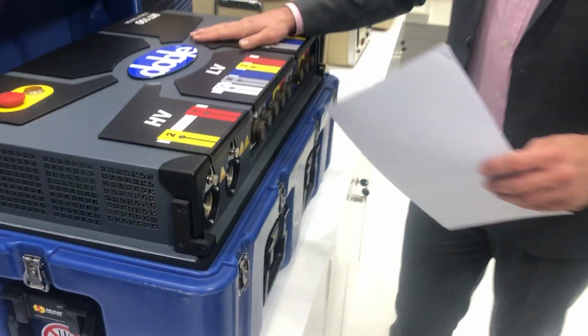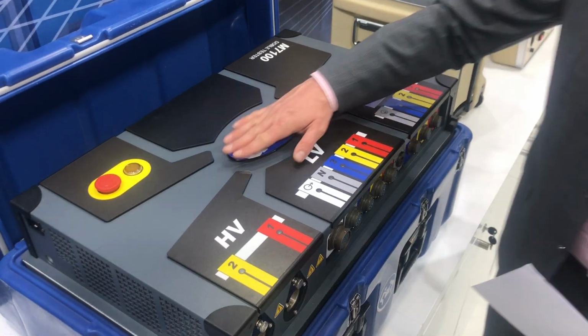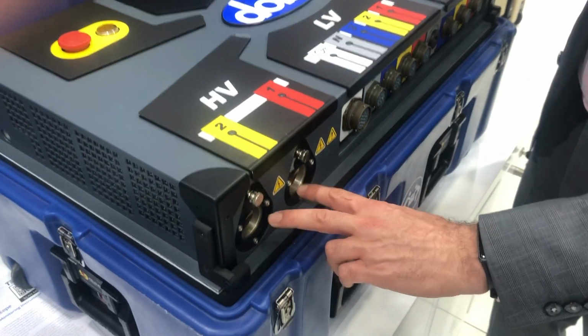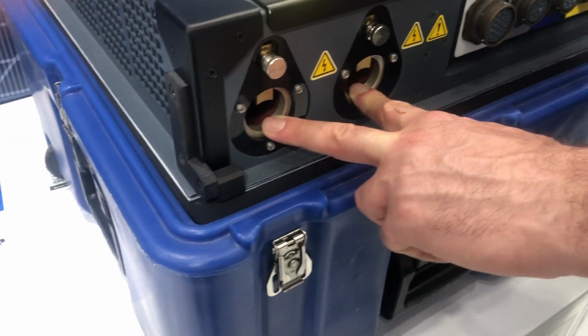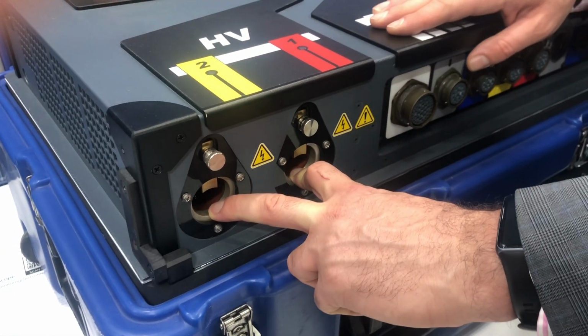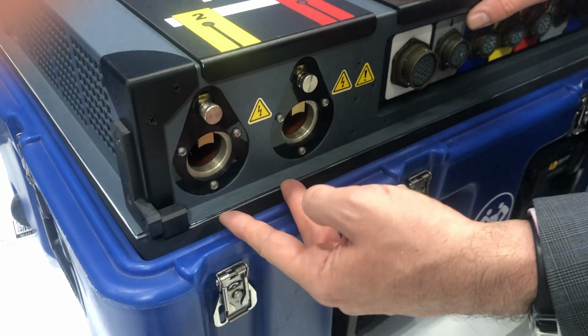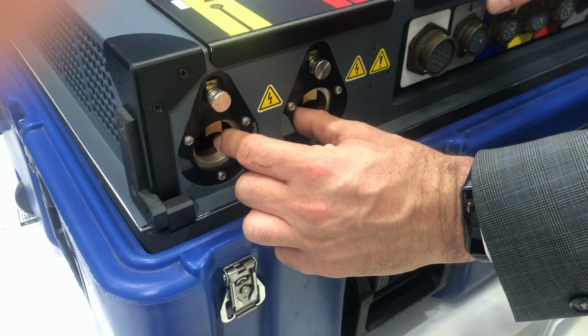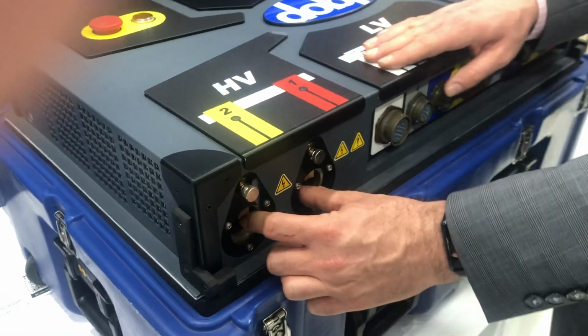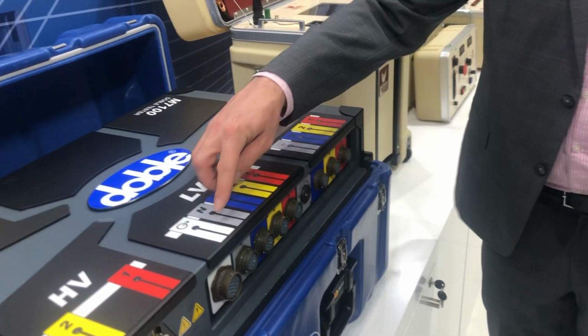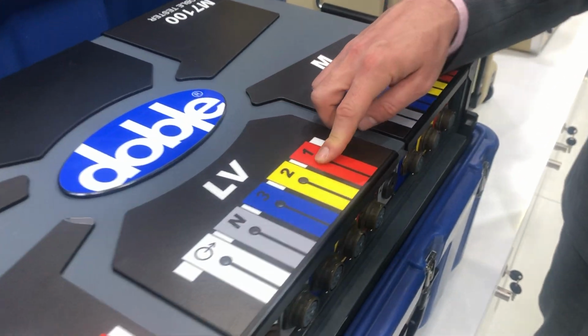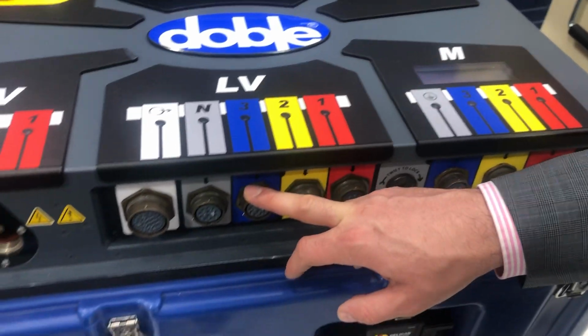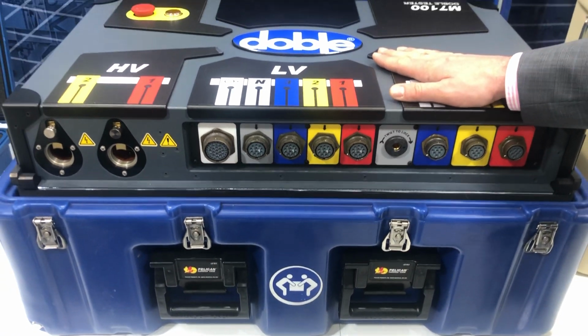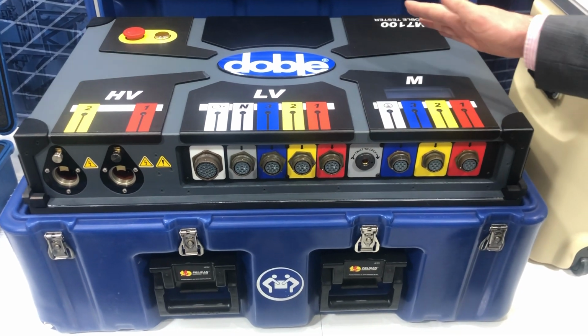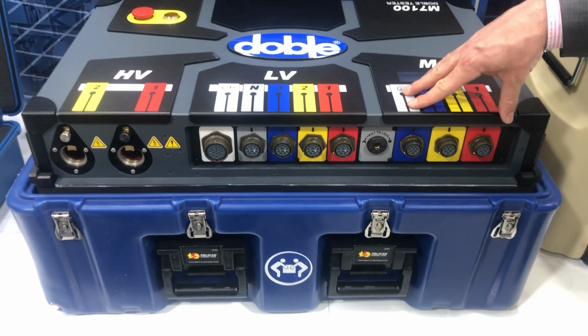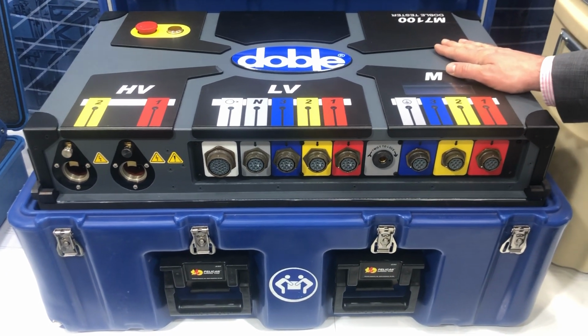The next device you're going to see is a real beast. So this is the only device for transformer testing which has two high voltage outputs, which would mean that when you're testing the tan delta or a power factor or DF, you don't need to change the connections from high voltage to low voltage. Everything is done with one connection, which means you reduce the time you need to go up and down the ladders. It is also a three-phase device, which means you can do a three-phase test of ratio and polarity as well as the winding resistance. The device also does short circuit impedance and no load test. So this would be low voltage generation and the measurement. M7100, a real beast of a device.